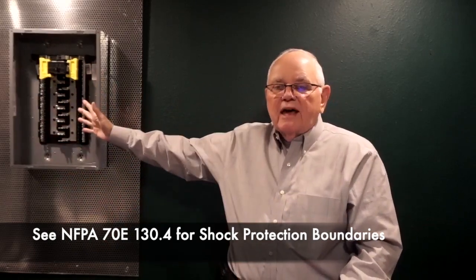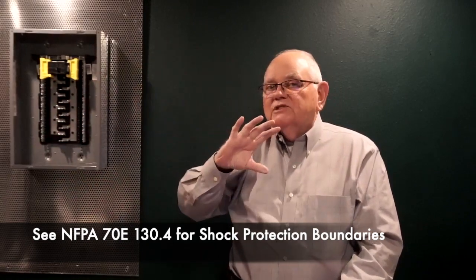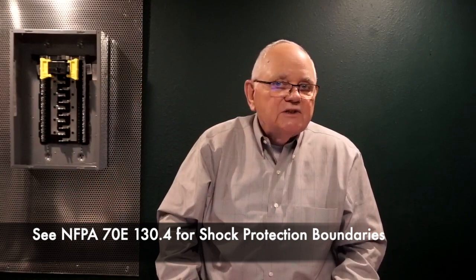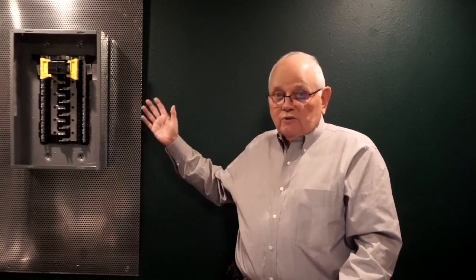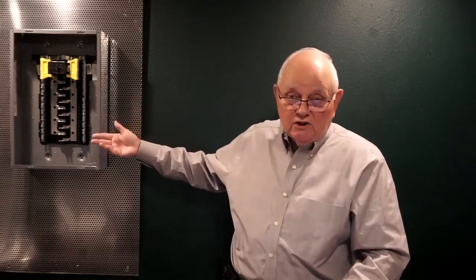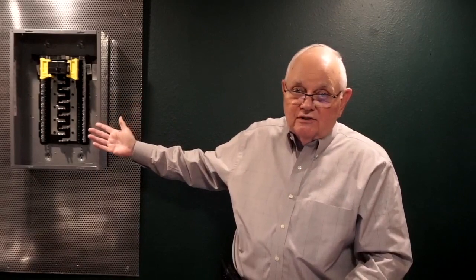So this is a single phase panel board. And yet the tables in 70E give me the voltage levels phase to phase. So what do I have to do? It says, take your phase to ground voltage, which would be 120 volts in a 240 panel board, and multiply it times the square root of 3, which it gives you in the 70E standard right beneath the table as 1.732. So if I multiply 1.732 times 120 volts, I get 208 volts. And that's the voltage I would have to use to base my boundaries on. Now, my limited approach boundary would be 3 feet 6 inches. That's considered to be, as we said, the shock boundary.